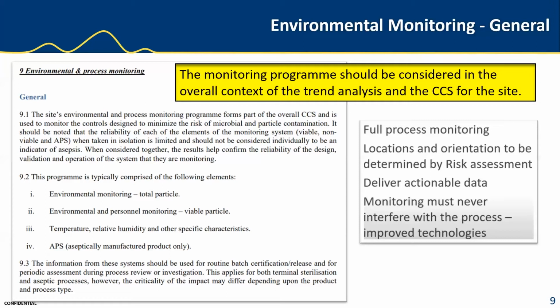And I need to just talk about this in a little bit of detail. It's really wise that you do a simulation of your system and your actual facility running as it should, and then with that simulation and the data that you're capturing, make sure you include all aseptic operations associated with routine manufacturing: equipment assembly, formulation, filling, even lyophilization if you're going to be doing that, the sealing process as necessary, and the validation that monitoring controls are in place and functioning as expected. That's important. We need to validate that.